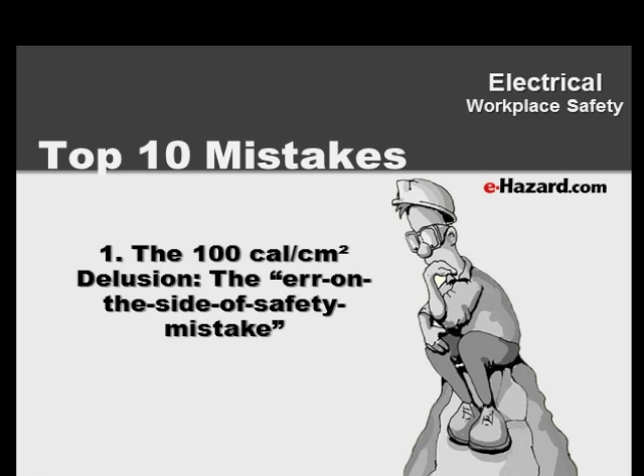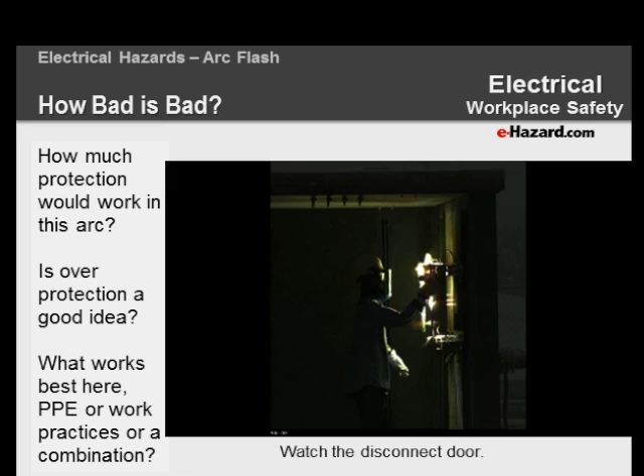One delusion we see out there all the time, in our top 10 mistakes: number one, the 100 cal delusion — 'I want to err on the side of safety.' We see companies buy extremely high-level PPE, bring in someone selling PPE to do their training, and end up scaring their workers or overprotecting them. One problem with overprotecting in arc flash is that you make workers hotter. We did a big study on contamination in arc flash clothing for an Ontario Mining Association, and found that sweaty, wet clothing is actually less protective from an arc flash burn than dry clothing. You want to protect to the level you've calculated, but not overprotect — overprotecting may actually decrease protection compared to putting workers in exactly what they need to wear. So sometimes people think erring on the side of safety means more protection, but you may wind up going the opposite direction without realizing it.